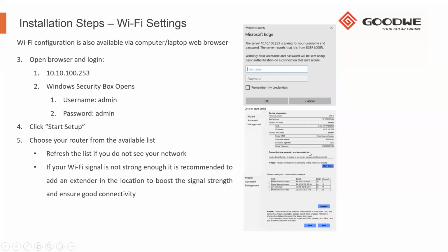And also, if you come into this page and it might not be in English, that does sometimes happen with older devices, you'll see on the top right corner there's an English button that you can click, then it will all be English for us. So we then click the blue Start Setup button. You'll see the inverter will then scan for local available networks. We can then check for the customer's network name. We look at the RSSI tab, because this RSSI is the actual signal strength.